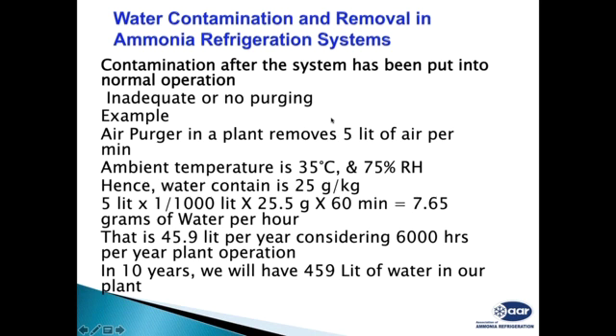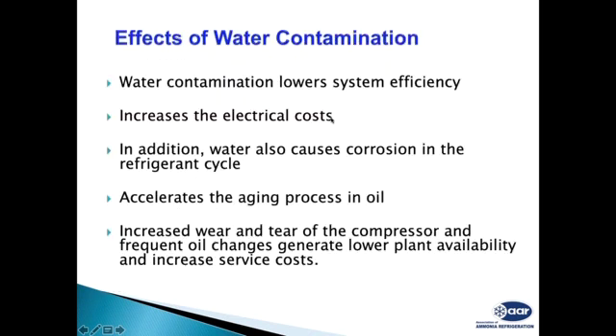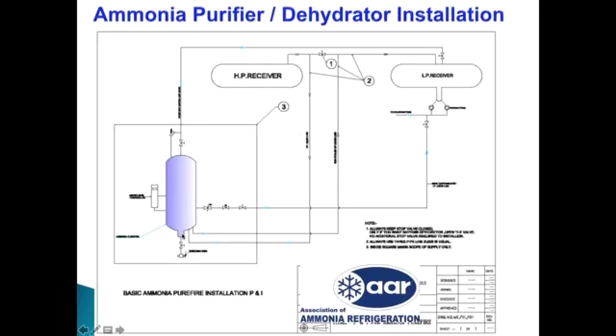You can use an ammonia dehydrator system to remove the water. This dehydrator is connected in a plant which is running continuously. So whenever the water accumulates at the bottom, you can drain it into the bucket using this dead man's valve with the safety system. If there is no water, the vessel will always be full with ammonia, so you don't have to drain. But once water has accumulated in the system, you can drain it while your plant is running.